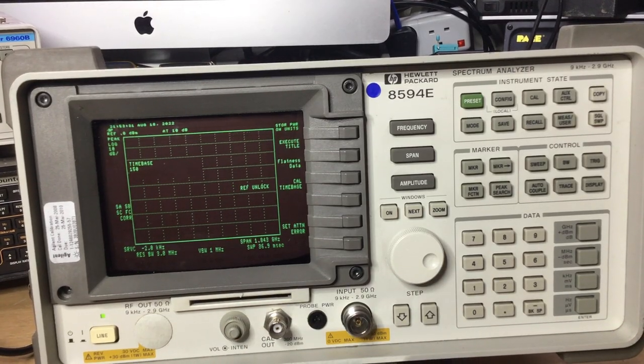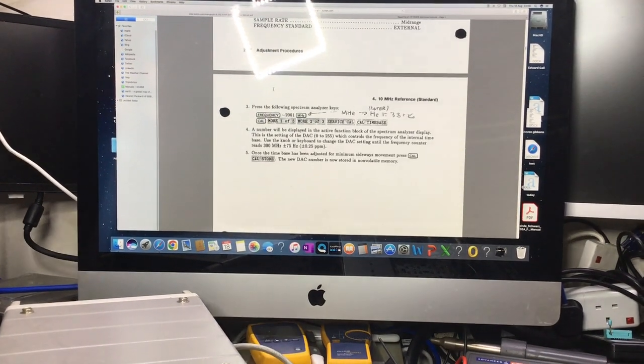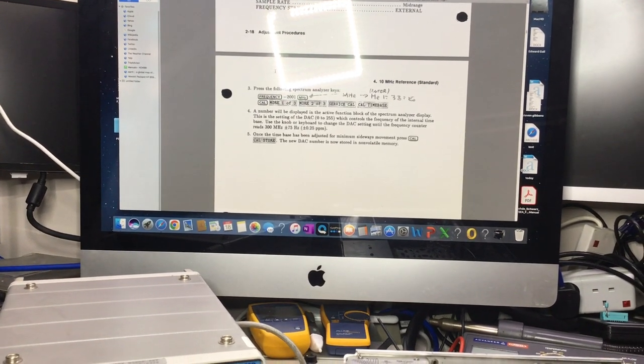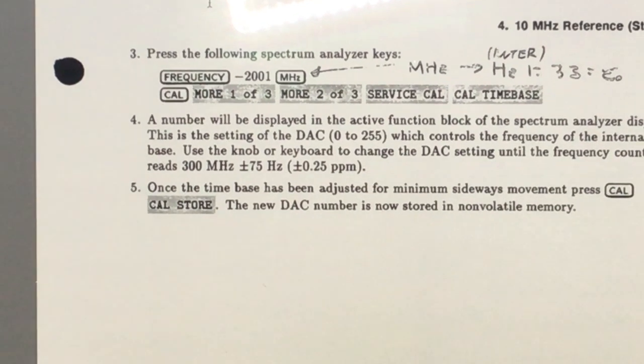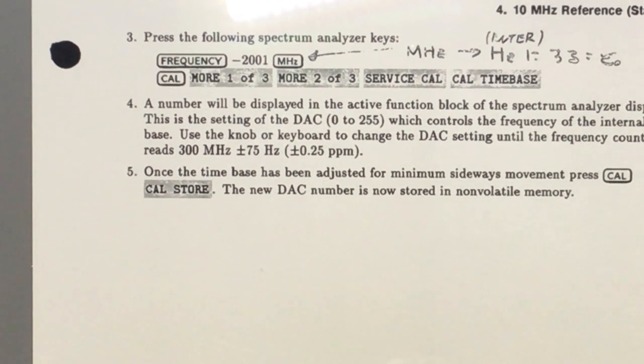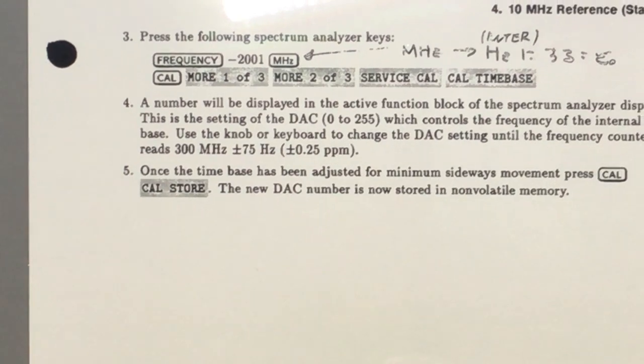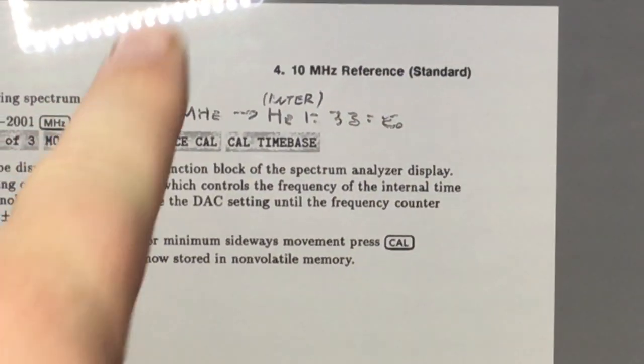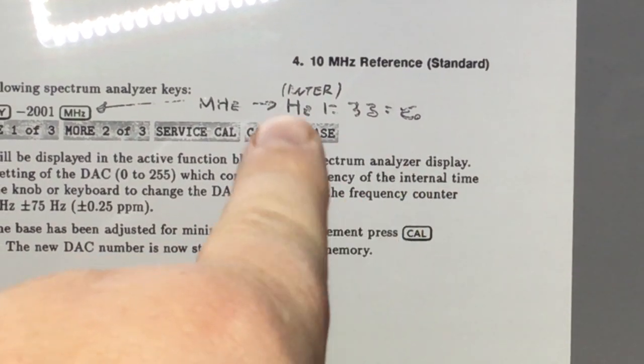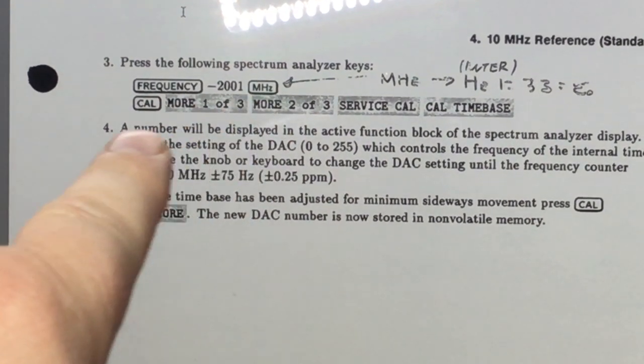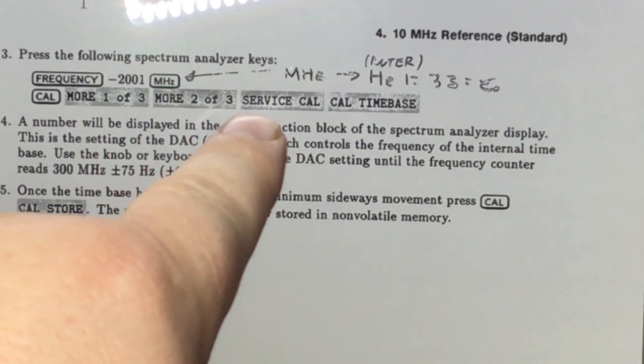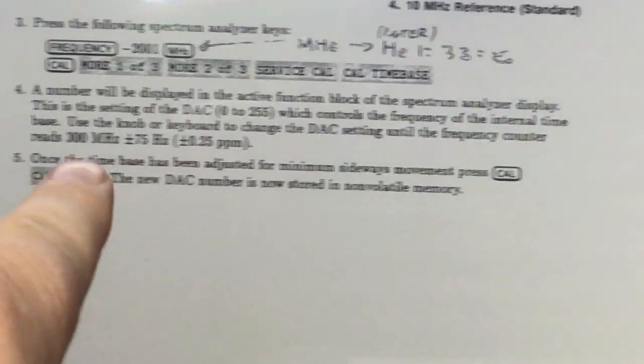There we are. So, although the service manual gives reference to megahertz, it's not actually the megahertz key at all. It's a hertz key, so entering -2001 hertz. Although there is a manual reference here to another code as well, which you might have to look at. It basically says enter that frequency first, then press the cal button, more 1 of 3, more 2 of 3, then service cal, then cal time base. But that megahertz is hertz actually.